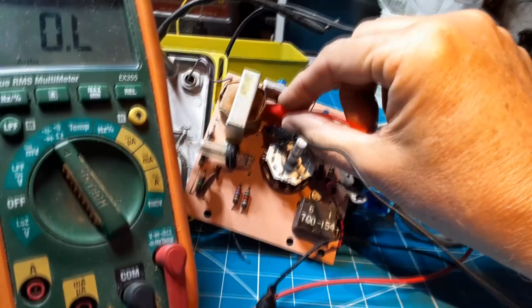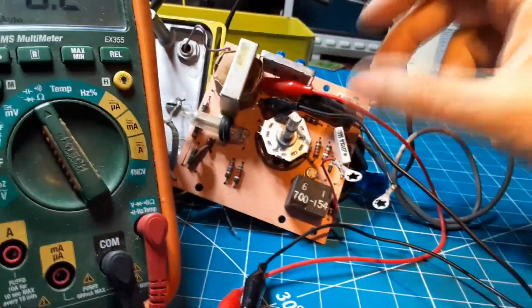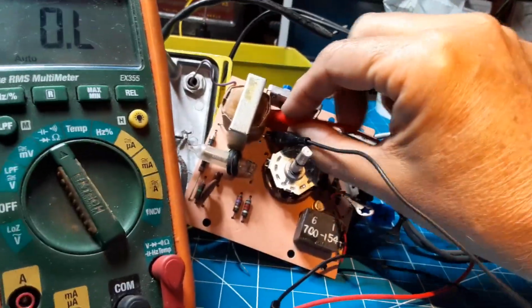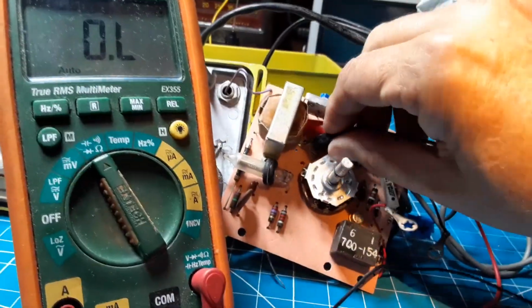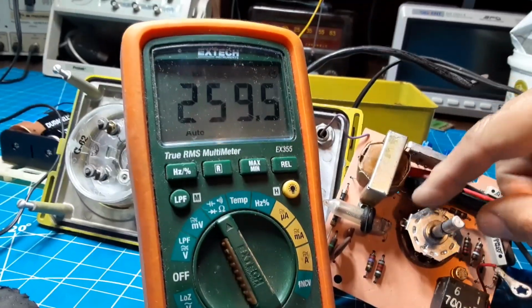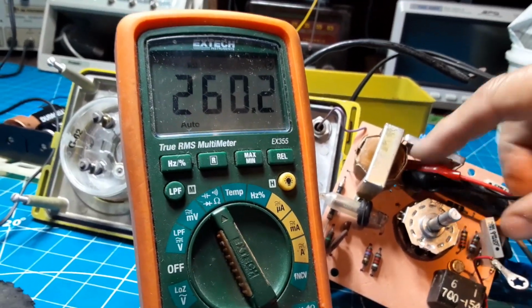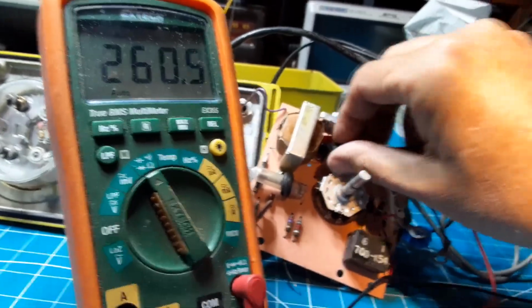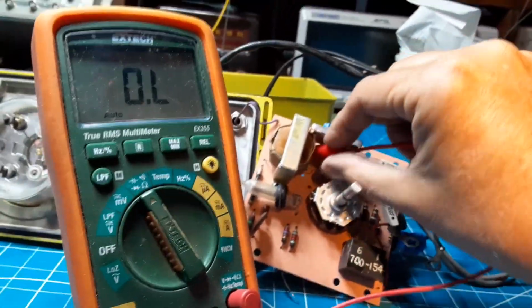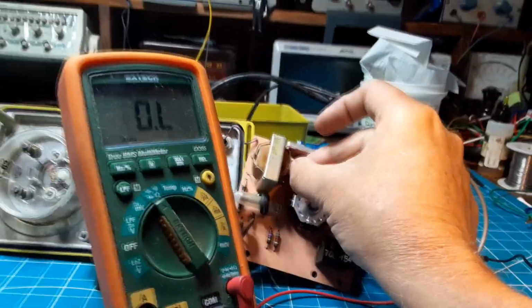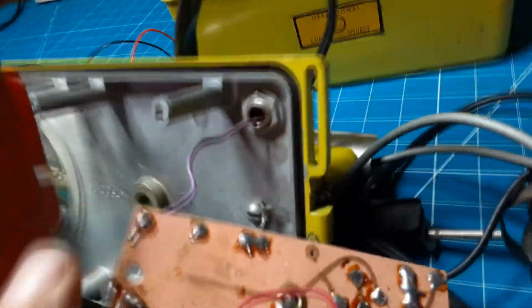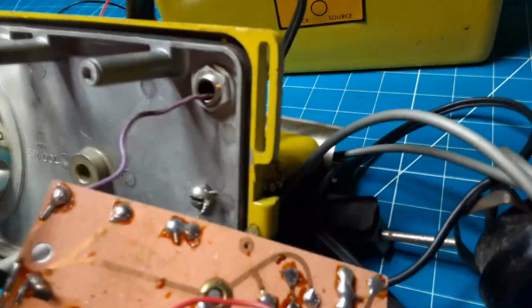And of course, if we get an open load there, then there's really no sense in checking the center one, because it's open load too, right? It has to be. Already checked it, and it is, of course. It has to be because there's connectivity between these two. So any one of those to here is irrelevant. You're going to get two different readings if it was good. So the transformer is bad. Now, I only lifted that one, found the problem with that part of the circuit. And so you can see it's still the original solder joints. I haven't taken it out.